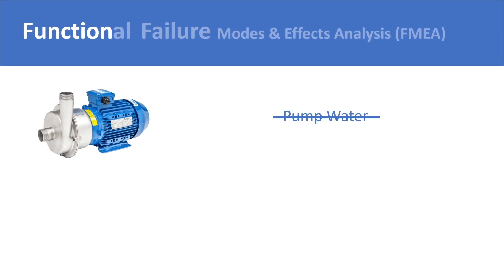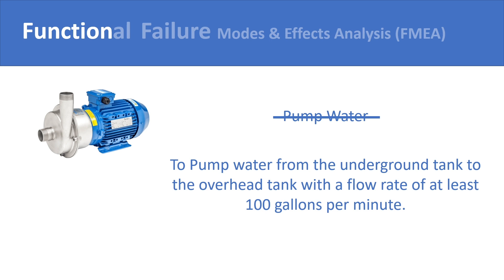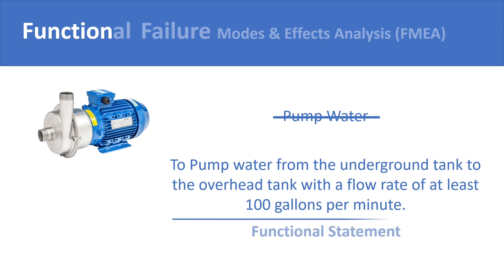In FMEA, the function of a machine has to be described in detail by describing exactly what the machine needs to do. Moreover, you also have to specify the performance standards. For example, a pump's function will be to pump water from the underground tank to the overhead tank with a flow rate of at least 100 gallons per minute. This is a functional statement in the context of FMEA — it clearly describes what the pump needs to do and lays down the performance standards expected from it.